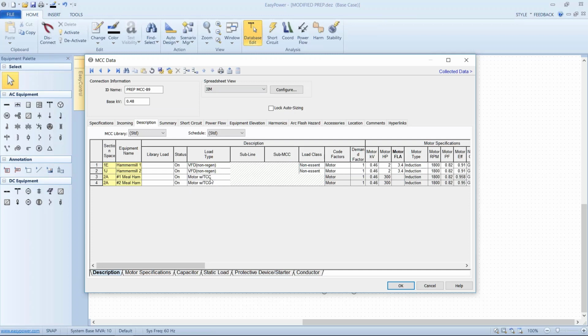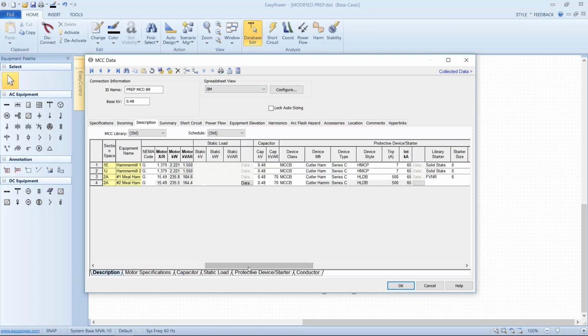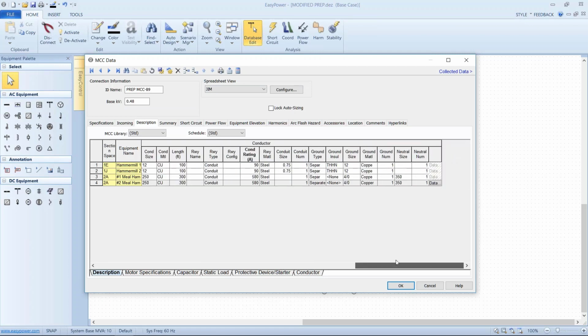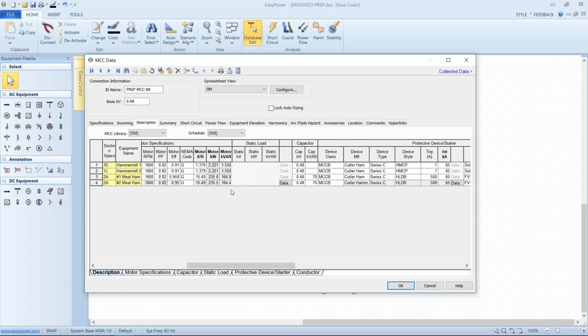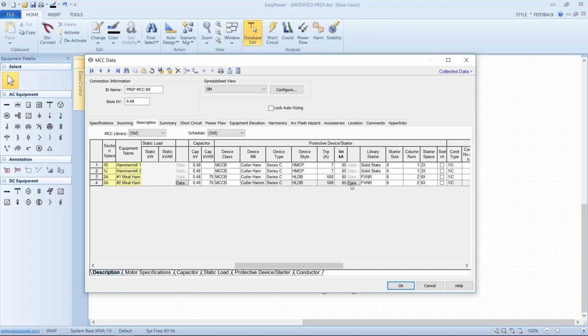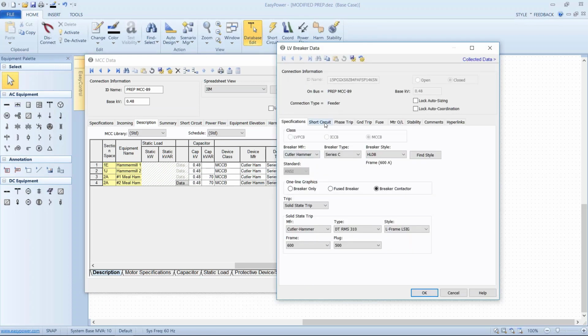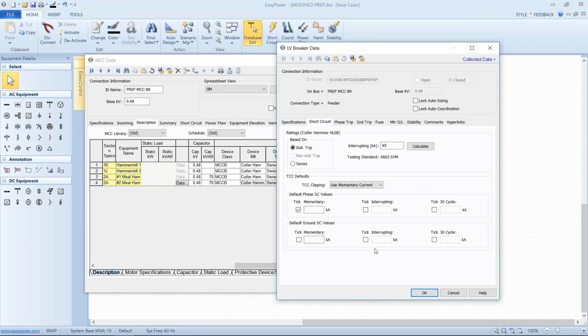Well, for starters, having multiple TCCs, especially if they're the same size, and they were chosen because they were both 300 horsepower motors, it's a duplication of effort. In some cases, it's more confusing. So the first recommendation I would have is to just have one motor with TCC on there, and the other isolate as a standard motor. And to do that, we'll calculate the full load current, and everything else should be good in terms of the data that was entered. And now at this point, we have a TCC, we have the motor and the breaker data, protective device, that was entered with our data entry button, and we seem to have everything kind of figured out.